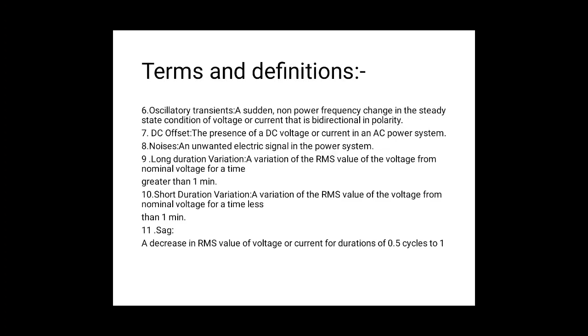There is another definition, swell. It is similar, but swell is any increase in the voltage for 0.5 to 1 cycle, known as voltage swell. Next, under voltage: 10% below the nominal value for time greater than 1 minute. We already saw long duration variation, where the RMS value varies from nominal value for more than 1 minute, but here it is a decrease in the voltage of 10%. If we consider a 230 volt supply, then 10% is 23 volt.